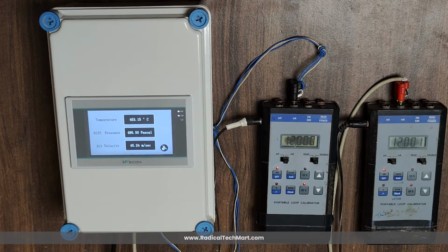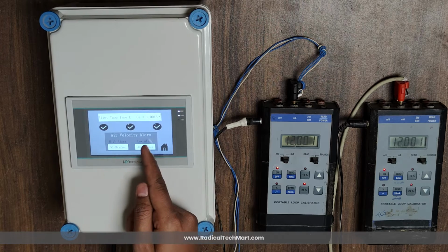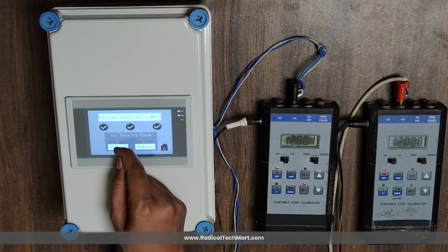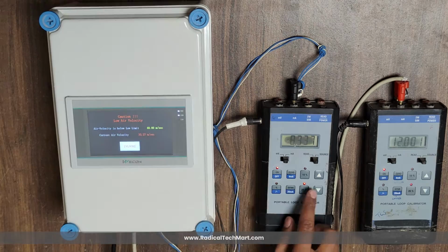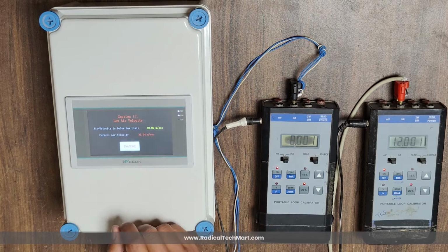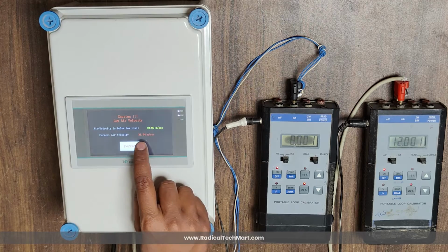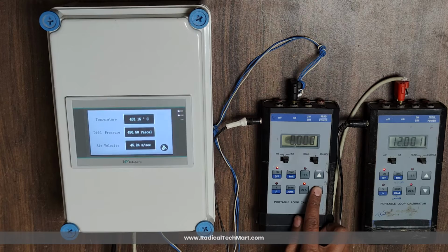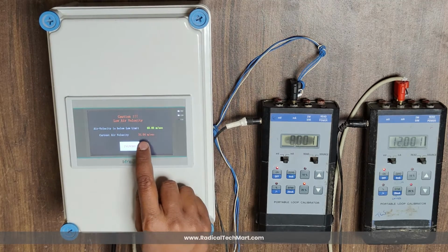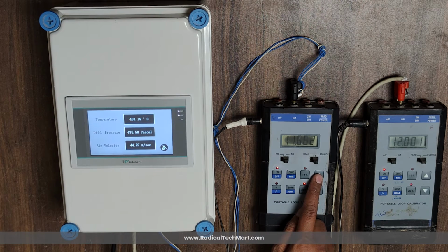So for the working tutorial, we have 2 analog input sources which are already connected to the panel. We have set the range as per requirement, and we have also set the high alarm value and low alarm value. Now by simulating the current, we can see that the values change, and as the value reaches the high alarm point, it shows the warning message as shown right now. Similarly, for the low alarm value, it will also show a similar warning message. Next, if we change the device constant, then we can see that the air velocity value also changes as per the selected device constant value. So this was about the working of the PLC-operated process panel.